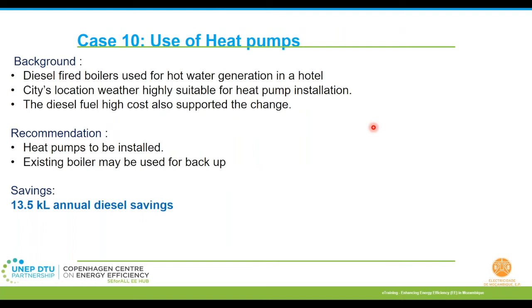Last case, use of heat pumps. This is another hotel, in slightly warmer climatic conditions. They were also using diesel-fired boilers to generate hot water requirements. The city's location and weather conditions were quite suitable for heat pump installation. So why not? We recommended installing a heat pump integrated with the existing boiler. And of course, the high diesel costs were also supporting the change. By installing the heat pumps, integrated into the existing boiler, to generate the required hot water for the hotel usage, they were able to save about 13.5 kl of annual diesel.